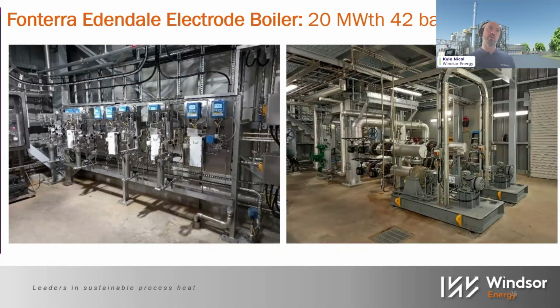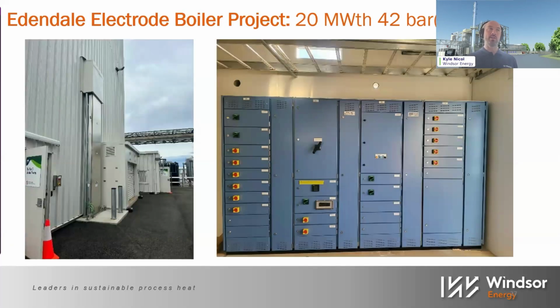Drivers for this project were that the existing boiler asset condition creates significant production risk, which exposes 2 million litres per day of milk processing. So they needed to deliver this project in under 12 months. Additionally, the site needed to reduce reliance on a low quality lignite fuel. And also they needed to reduce the carbon footprint of their production.